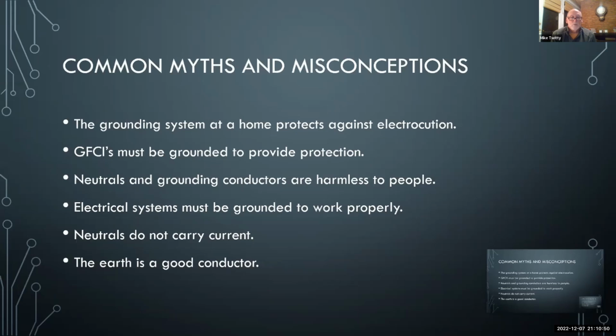Okay, electrical systems must be grounded to work properly. That's a myth too. When I was working in industrial at Ford, we had ungrounded 3-phase delta systems. That was done intentionally for critical circuits, power circuits, where you have a lot of water and a lot of problems in manufacturing and big industrial plants, and things get grounded quite often. If one phase gets grounded, it doesn't shut you down. It gives you a warning, and you can troubleshoot it and repair it at downtime, but it does not shut you down. So their electrical system can work without a ground. Neutrals do not carry current, like I just discussed. That's not true. And the earth is a good conductor. Not true also. It's a high resistance, but it is a conductor.